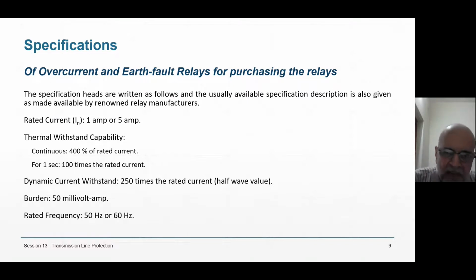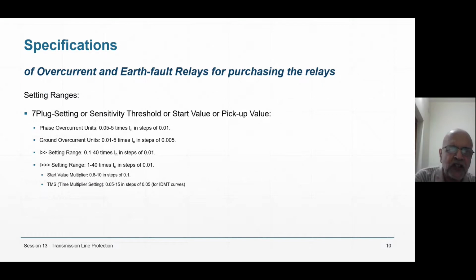Dynamic current withstand, that is half wave value. Up to half wave, 10 millisecond, it can withstand 250 times the rated current. Yes, this 250 can vary from manufacturer to manufacturer. This is just from one manufacturer I have taken. But mainly you have to ask for dynamic current withstand. Burden 50 millivolt ampere. Rated frequency 50 or 60, because in foreign countries 60 Hz is used.